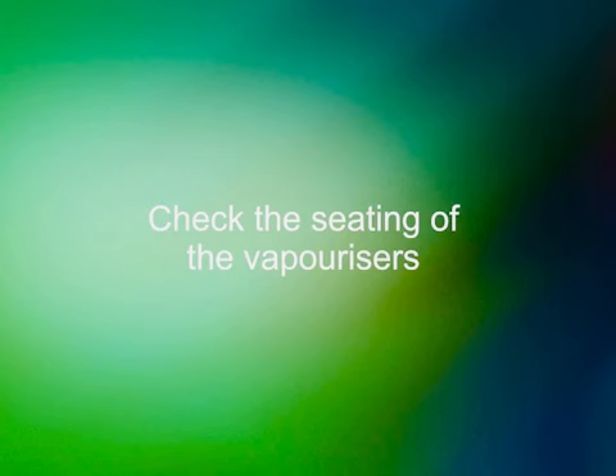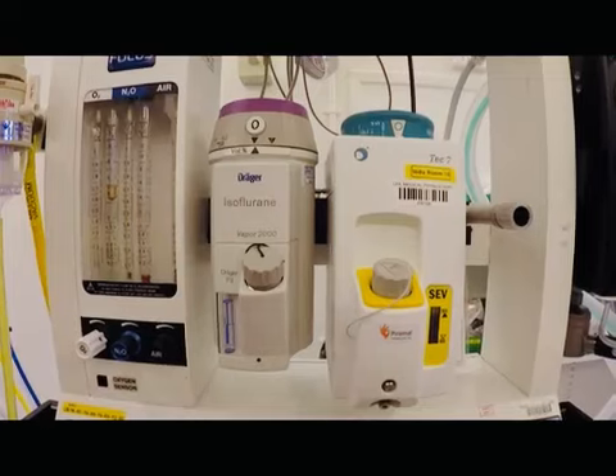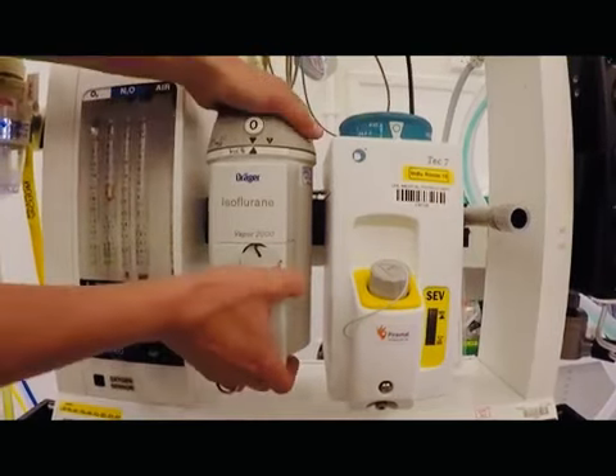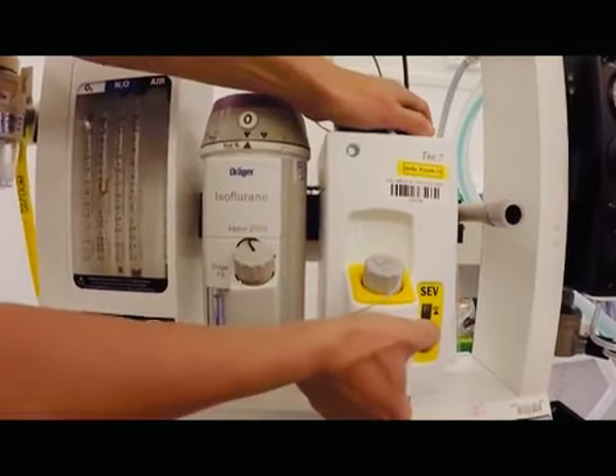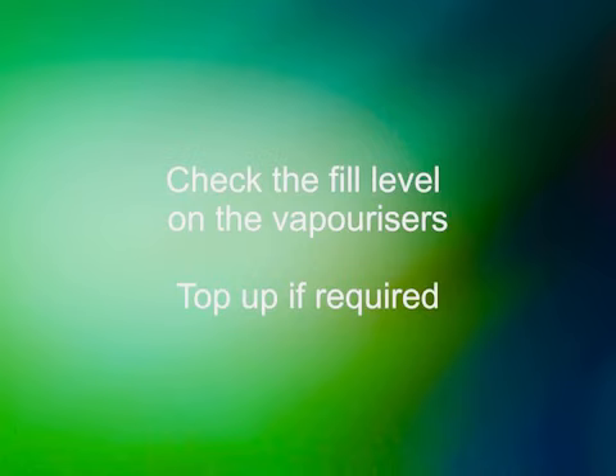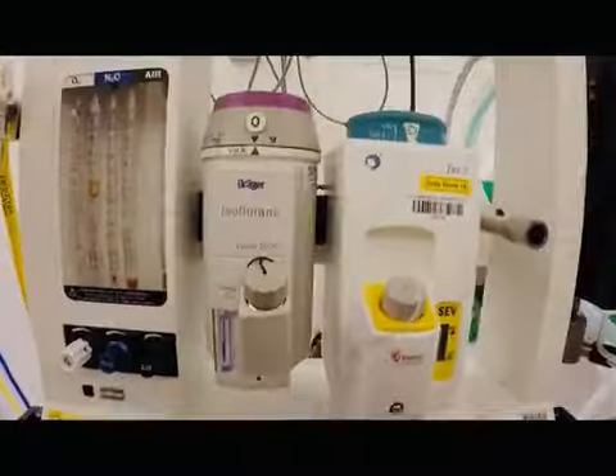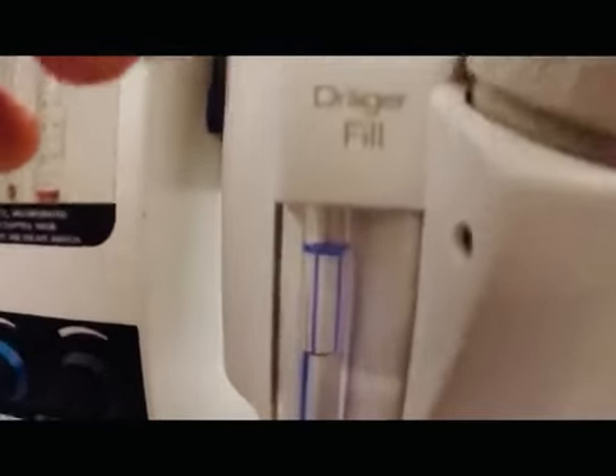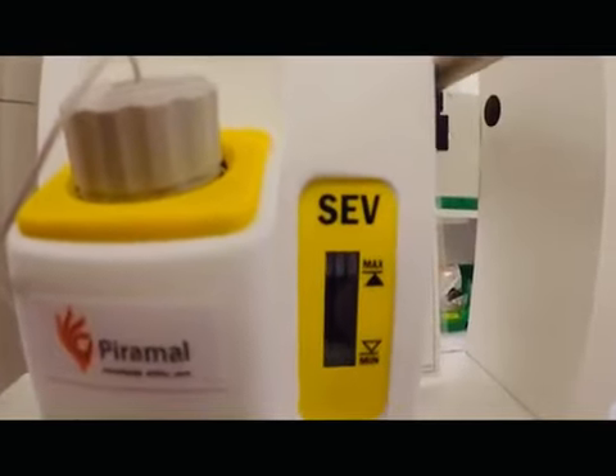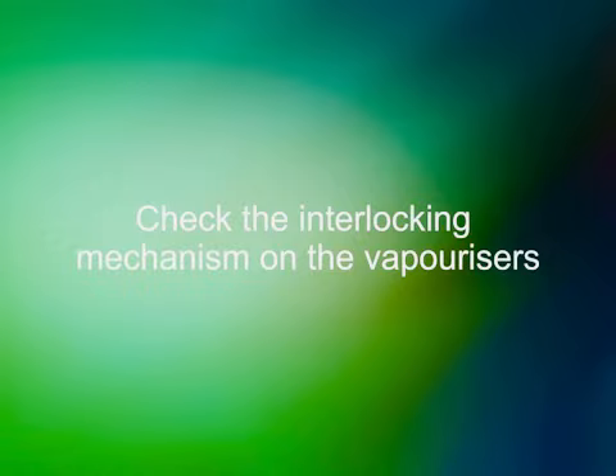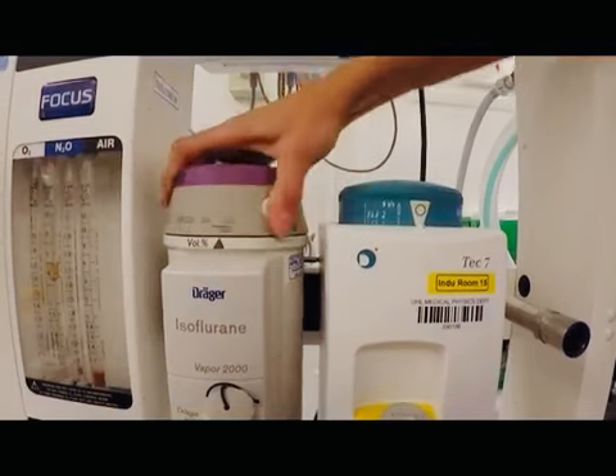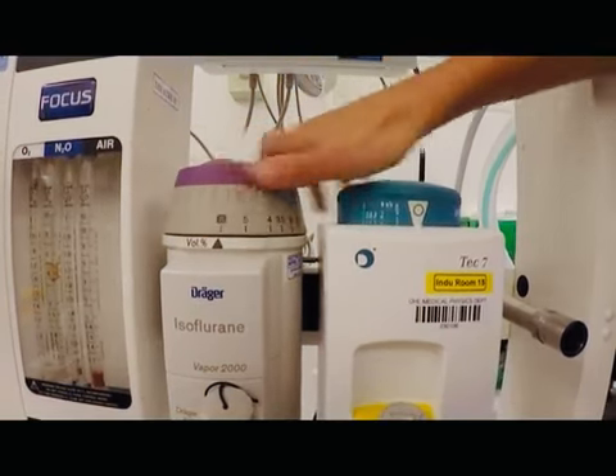Check both vaporizers are seated properly and adequately filled. Check each vaporizer switches on throughout its range and that the interlocking system is working to ensure only one vaporizer can be used at one time.